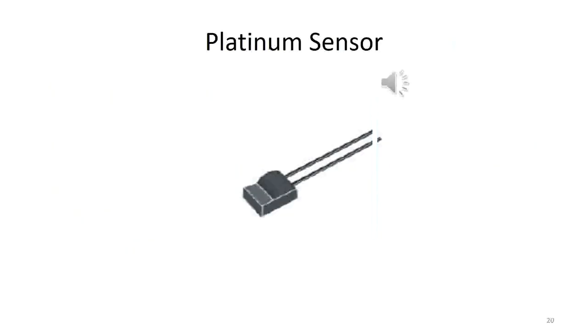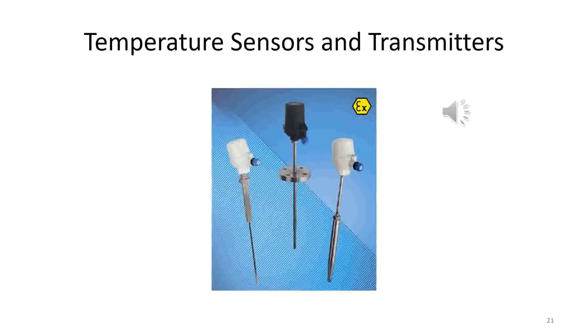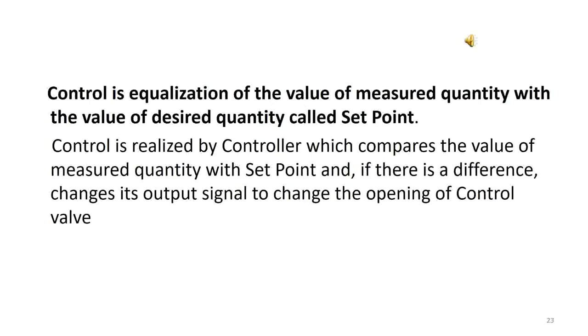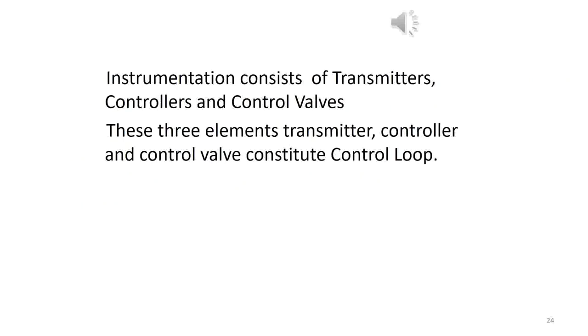Platinum sensor. Temperature sensors and transmitters. All instruments function in this manner. Instrumentation consists of transmitters, controllers, and control valves. These three elements, transmitter, controller, and control valve, constitute control loop.